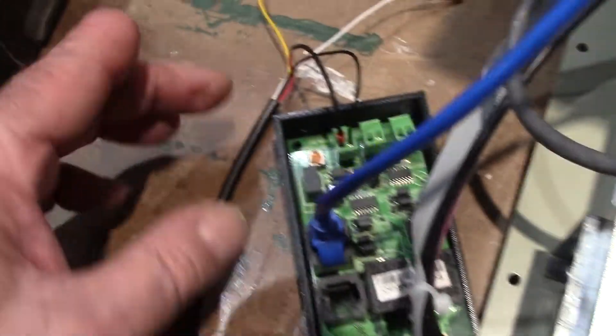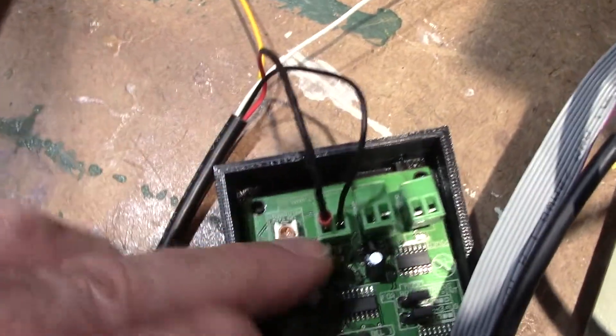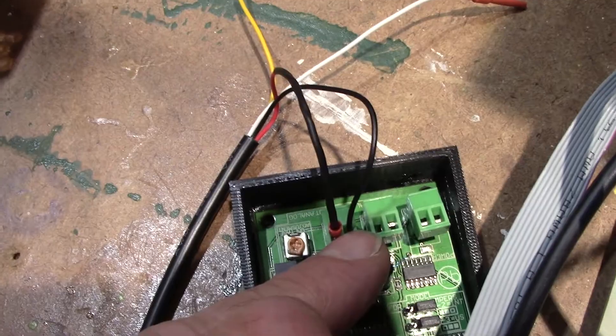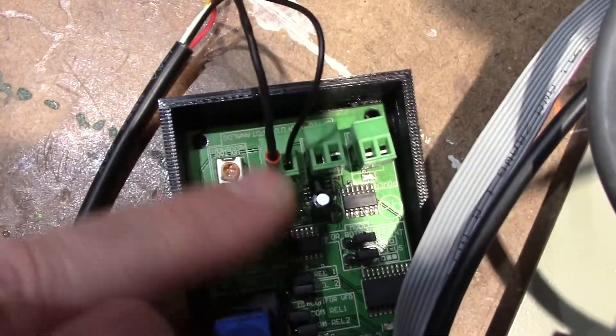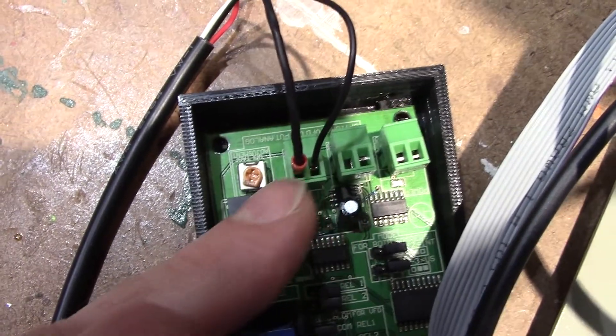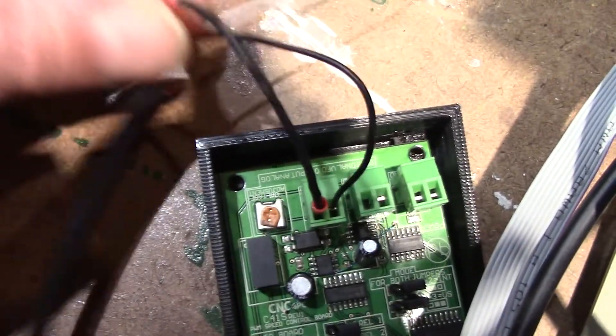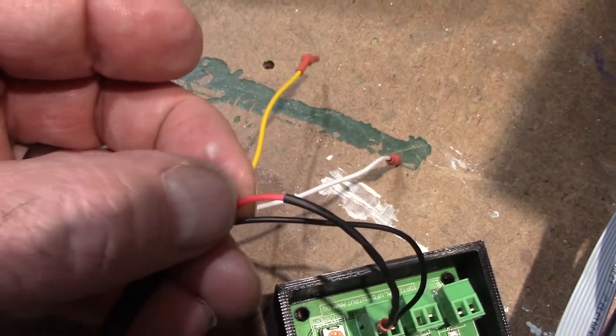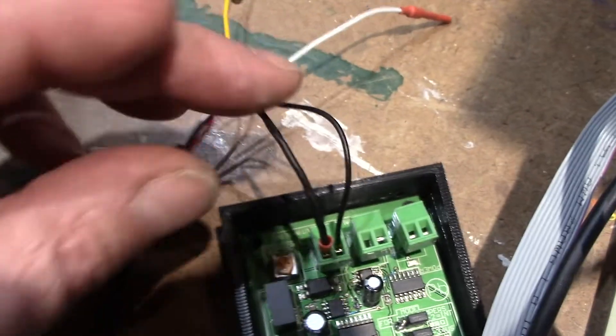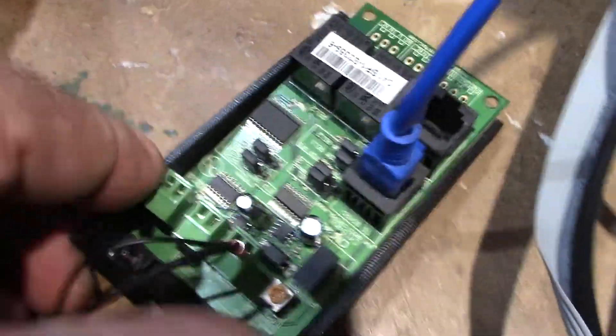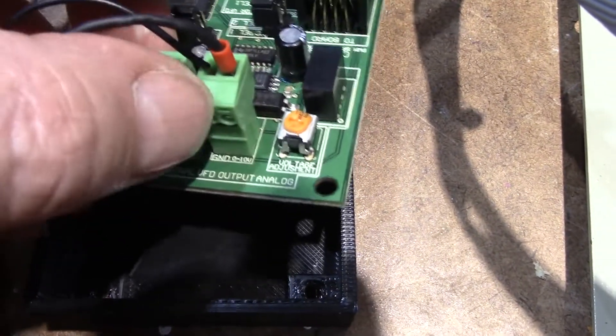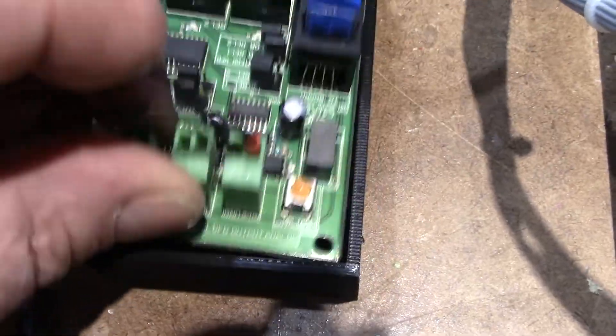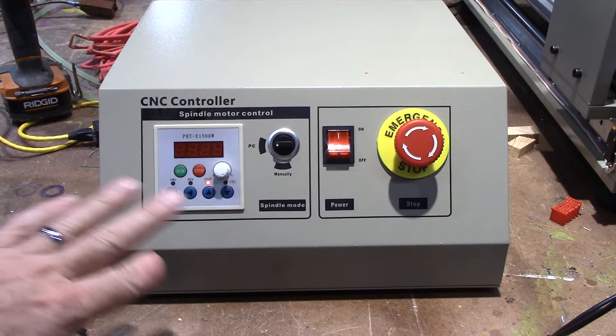Okay. So coming out over here is ground. So you take your black wire from here and attach it to this pin over here that says ground. And then this wire, it's actually the red one. For some reason they put that black case on it so that it looks like from here down, it looks black, but that's the red wire. And it goes to this pin right here that says zero to 10 volts right there. So you attach those two right there and that's got all your wiring done.